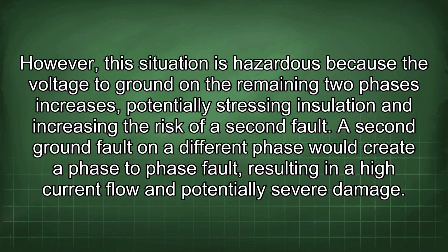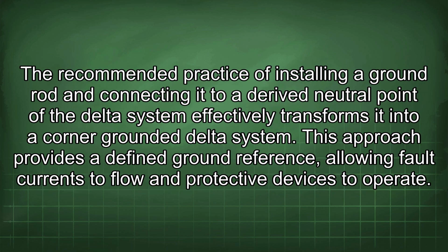A second ground fault on a different phase would create a phase-to-phase fault, resulting in a high current flow and potentially severe damage. The recommended practice of installing a ground rod and connecting it to a derived neutral point of the delta system effectively transforms it into a corner-grounded delta system. This approach provides a defined ground reference, allowing fault currents to flow and protective devices to operate.